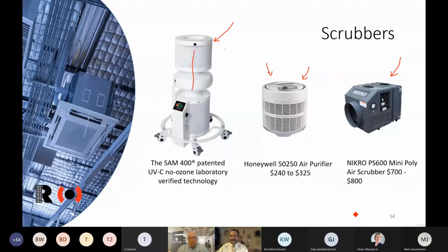I have a facility that I have people meeting in regularly. I've been doing this for months now, since March. I have scrubbers run inside my environment, and I measure the particles inside there. Believe it or not, when meetings are occurring, we either turn the scrubber down to its lowest speed, and in some cases we'll turn it off for the meeting, but then they're always put back on to scrub the air between meetings. Generally, the one that I have that's variable speed, we leave it on low speed the whole time and then ramp it back up. But we're controlling the particles well below the background, and that's the most we can really do.